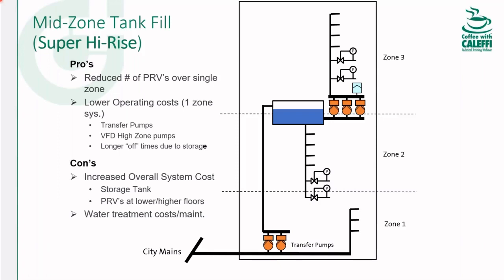So the design principle on those is that somewhere in the midway point, they have I think two floors worth of storing of the water. So there's a set of transfer pumps at the base of the building that transfer the water to the storage tank. So gravity feeds the lower part of the building. And then there's another set of pumps adjacent to the storage that supplies the upper half of that building. So this is a methodology for super high rise. I think the building in Dubai, the Burj, is 2700 feet tall. It's like half a mile. But anyways, that uses a similar concept there.